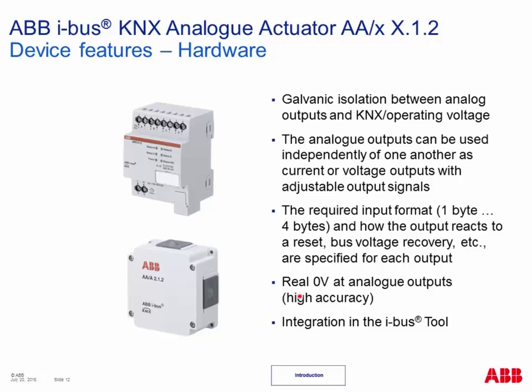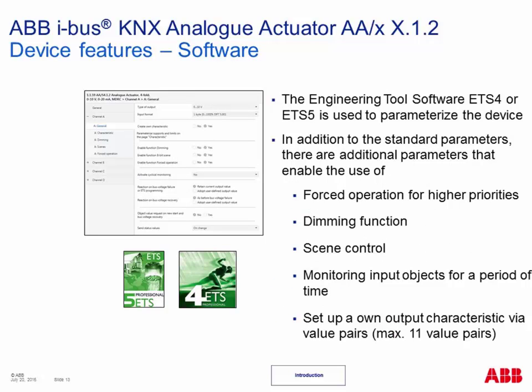And last but not least, as expected, we have integration also in the IBUS tool here available. So you will see later on from Jürgen how it works, what is possible together with the IBUS tool. Of course, it's a KNX device, so you have an ETS application available. Important is that we support ETS4 and ETS5, but not ETS3 anymore with this device. So for those who are still working with ETS3, it's a challenge. You need minimum ETS4 here.